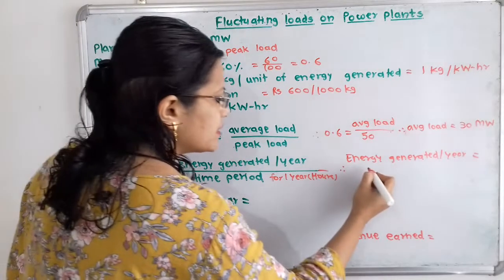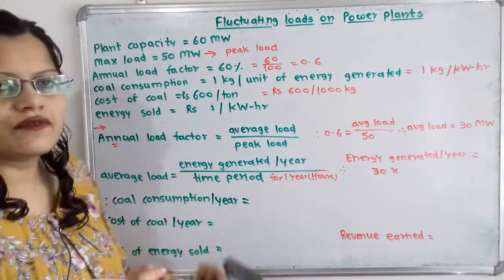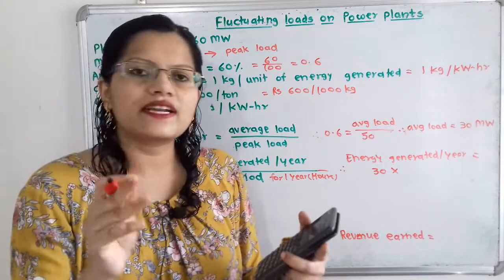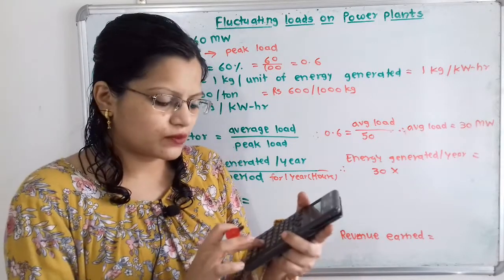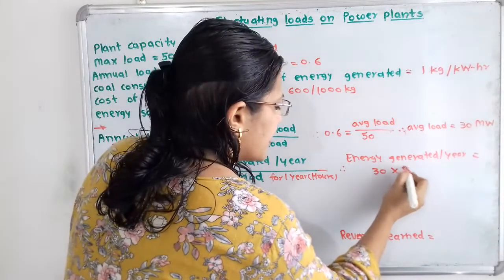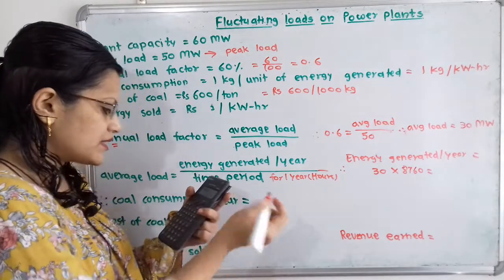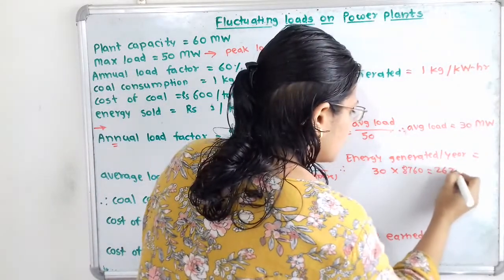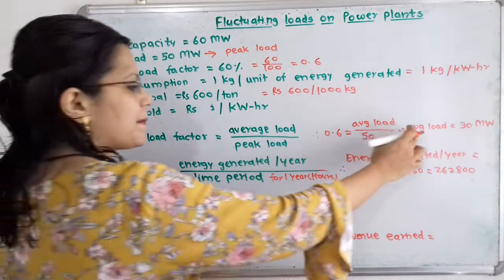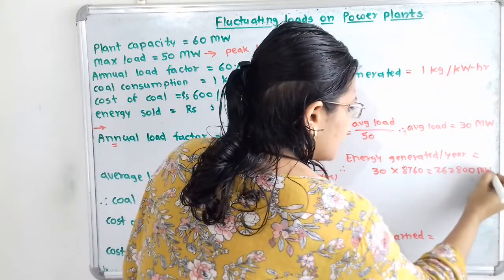Average load is 30 megawatt, multiplied by time period for one year: 365 days multiplied by 24 hours, which is 8760 hours. So energy generated equals 30 multiplied by 8760, that is 262,800 megawatt hours.